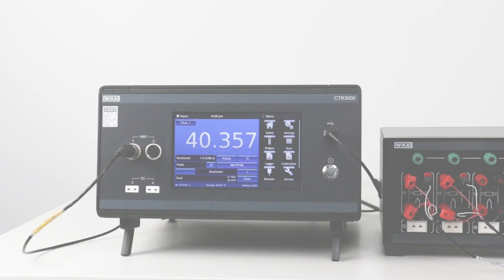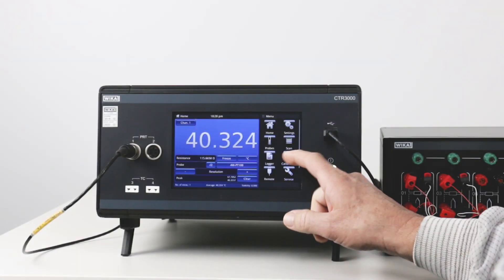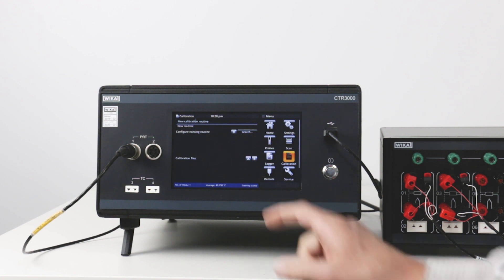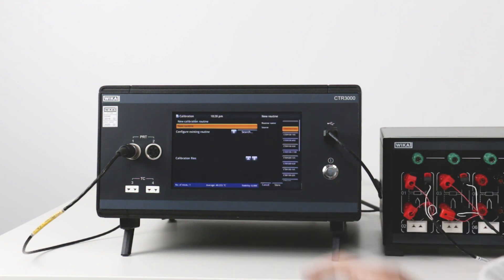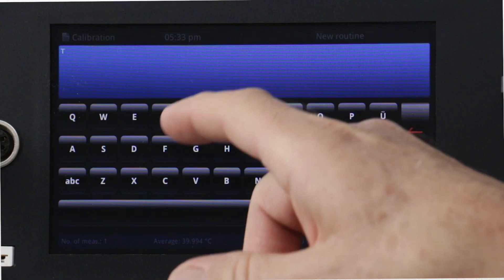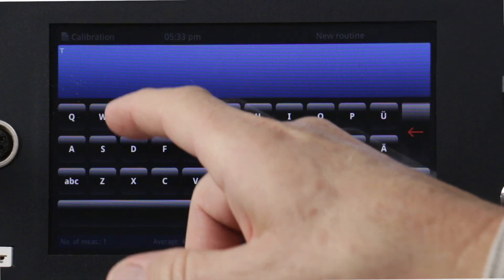An in-depth look at fixed point versus comparative temperature calibration methods is linked at the end of this video. The CTR3000 has an automation menu where all parameters are set in calibration test routines. Each routine can be named and saved for future tests.